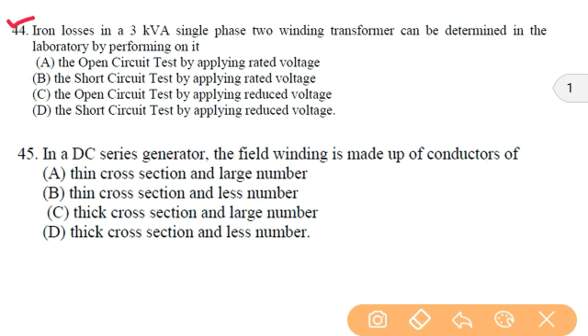In the next question, iron losses in a 3 kVA single phase two winding transformer can be determined in the laboratory by performing on it. So we can find the losses such as iron losses, copper losses by performing open circuit and short circuit on the single phase transformer. For iron losses we'll perform the open circuit test with rated voltage. For copper losses, we will short circuit by applying a reduced voltage. But here in this question, option A will be the correct answer, that is open circuit test with rated voltage.